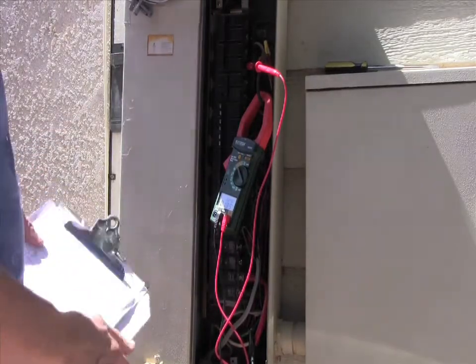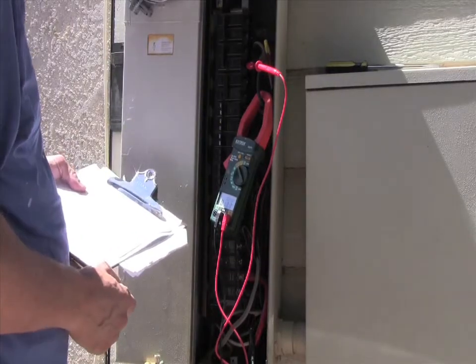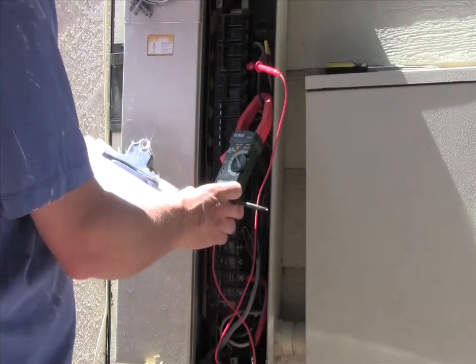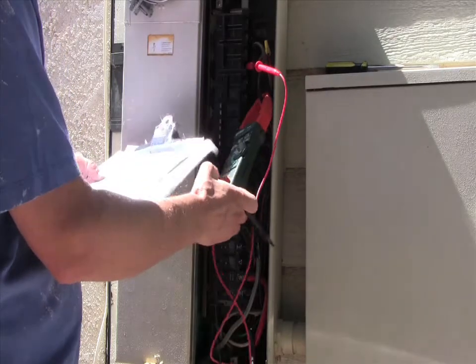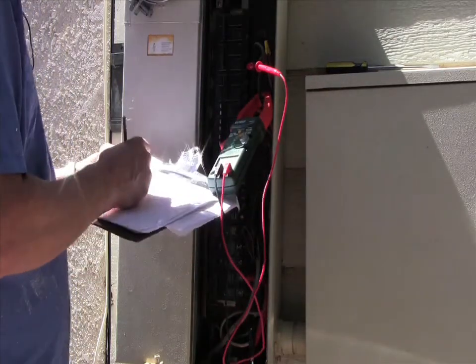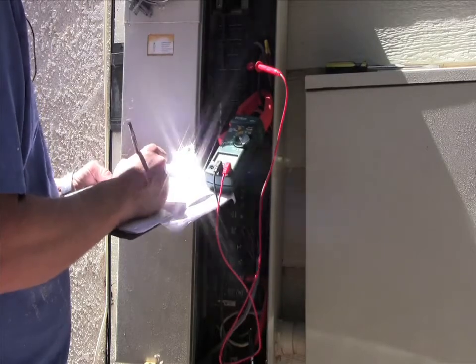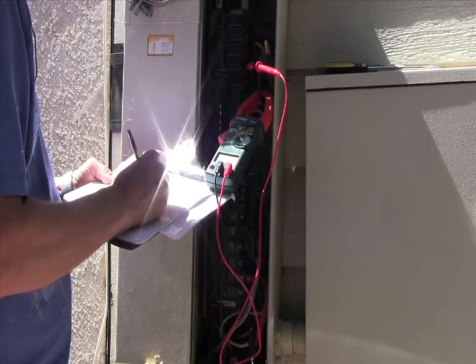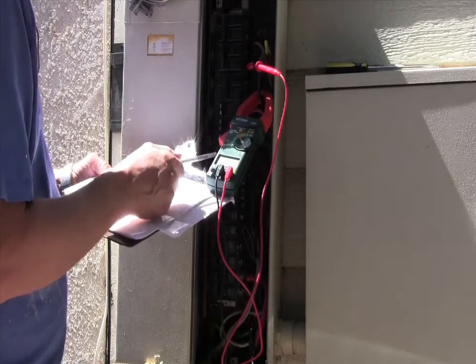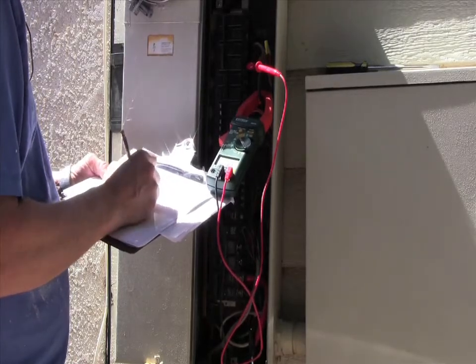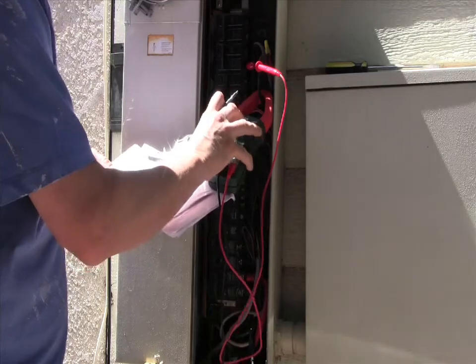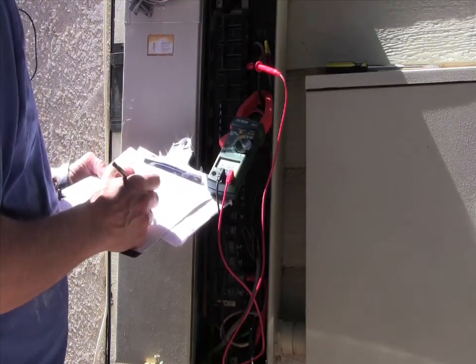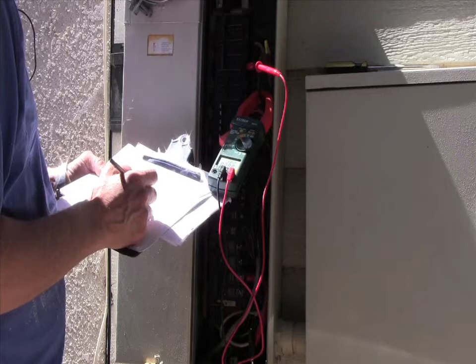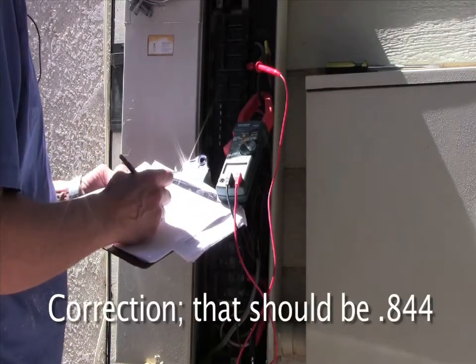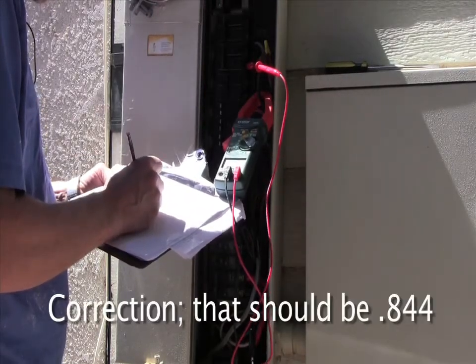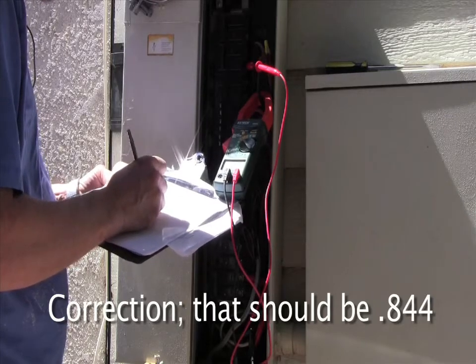Okay, so now that it's running, let's start taking our readings. It's been about 30 seconds. So this is on leg 1, and it looks like it's developing 2.5 horsepower. And it's generating 1.90 kilowatts. And we'll go to the next range mode, which is power factor, and it's showing 0.844 on the initial power factor, and it's lagging.